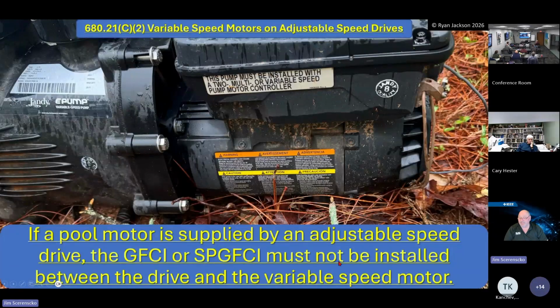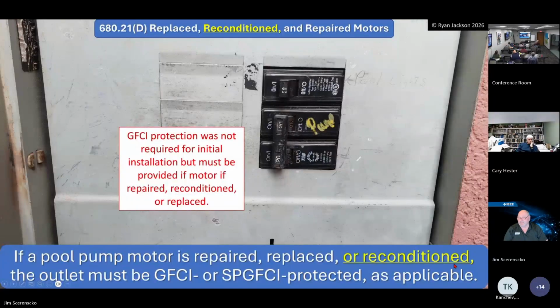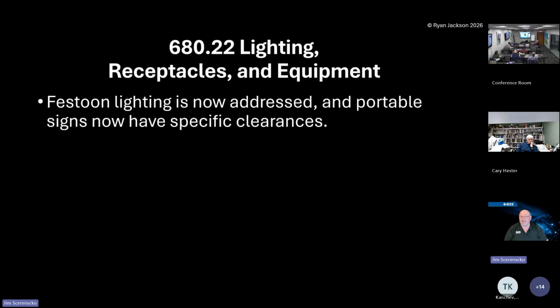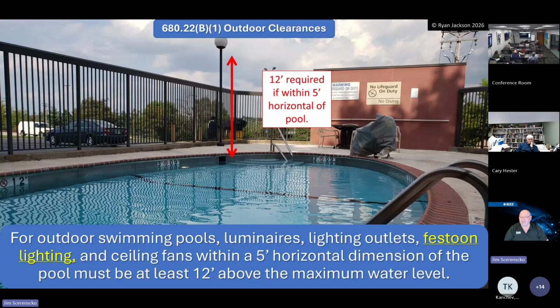If the pool motor is supplied by an adjustable speed drive, the GFCI or SP GFCI must not be installed between the drive and the variable speed motor. So you want to make sure of that, because it'll be a nuisance trip if you do that because of the frequencies. If a motor is replaced, repaired, or reconditioned, then the GFCI protection must be installed with the new motor, which we always enforced anyway. They added the word reconditioned in there.